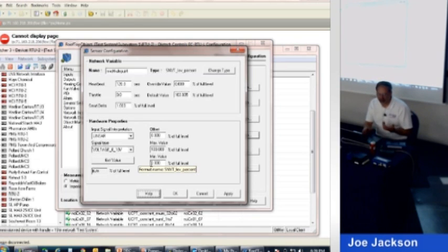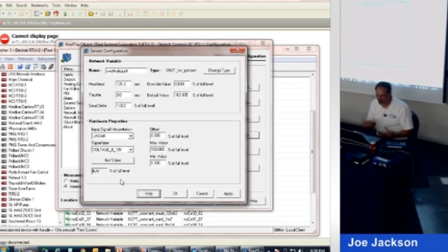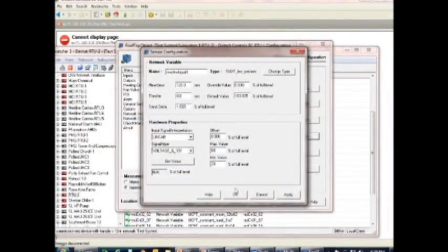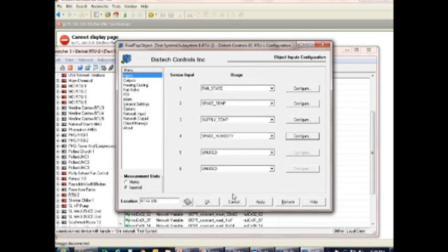If we were actually connected to a controller, which we're not, you could click this button and it would tell you what the current value of that sensor is. But let's say the humidity sensor only read between 20% and 80%, which is not unusual. It's not what we do, but if the humidity sensor could only read in that range, you could set it up for something different if you wanted. And just click OK, and it puts it in there. So, let's see what else we might want.